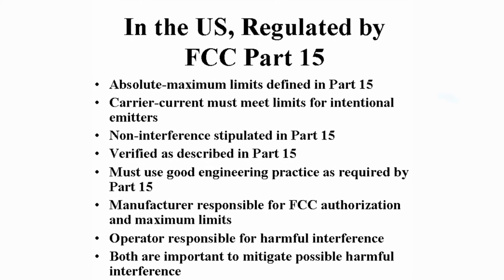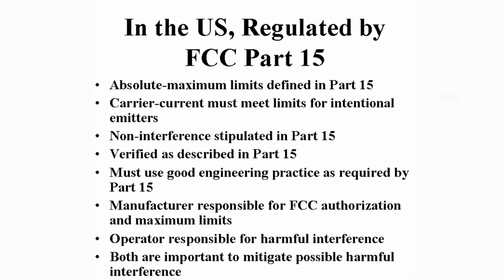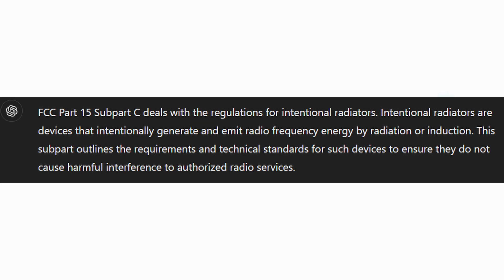Depending on where in the world your device is sold, you will have to adhere to a different regulating body's standards. In America, you have to comply with the FCC's rules and regulations regarding electromagnetic interference, detailed in Part 15 of their Code of Regulations. Depending on your device's intended use, you would comply with a specific subsection — for example, Subpart C calls out standards for intentional radiators such as RF transmitters and wireless communications devices. It's pretty common to test one device to multiple standards to ensure it can be used anywhere in the world, and in general most standards around the world are similar enough that this isn't much extra work.